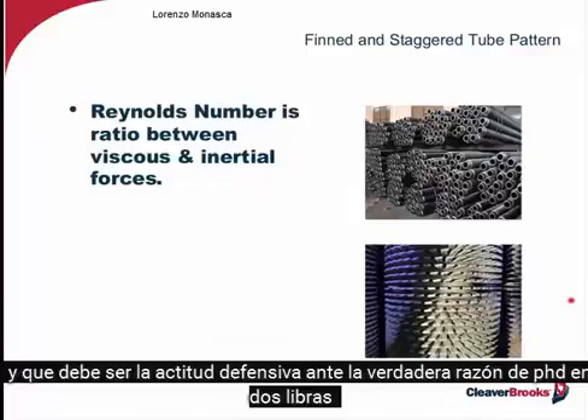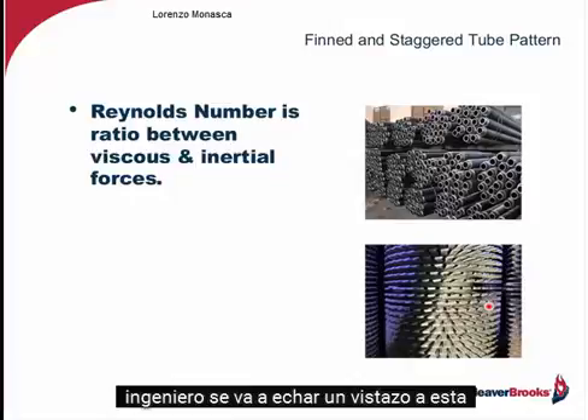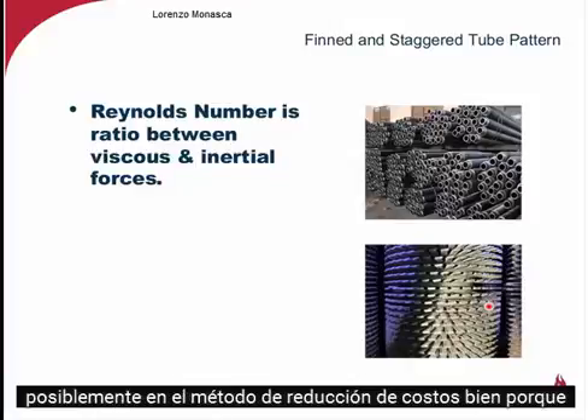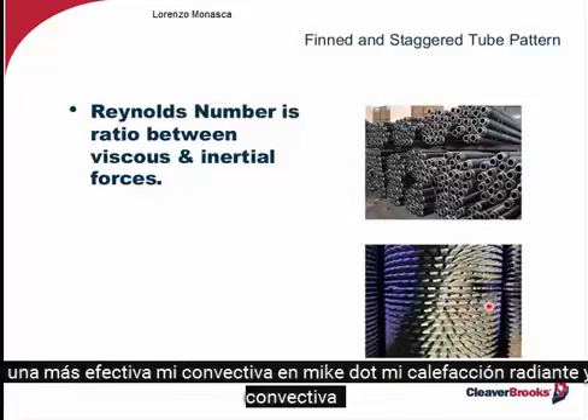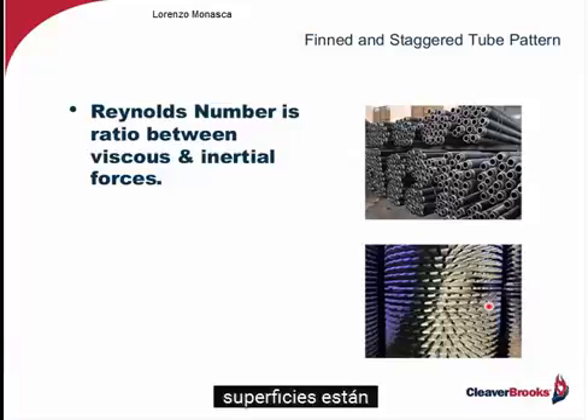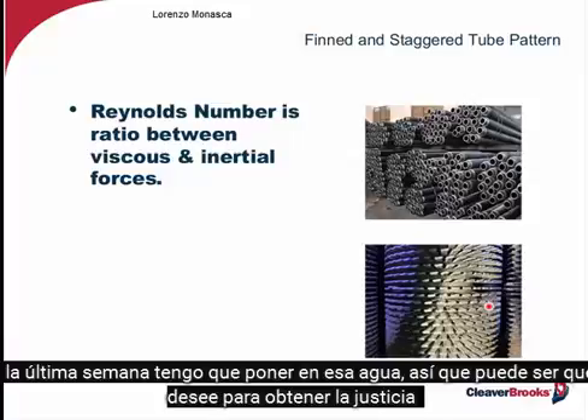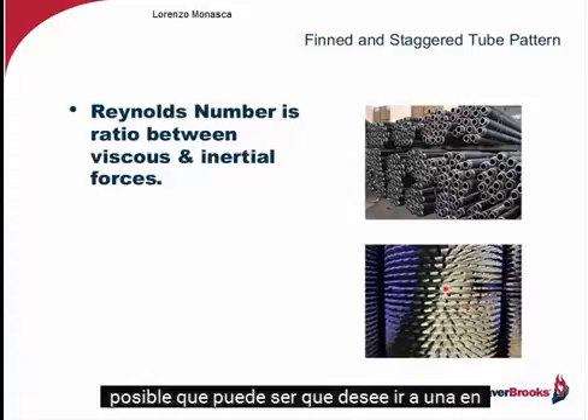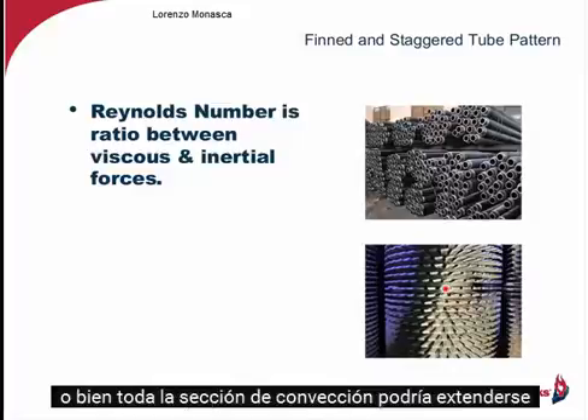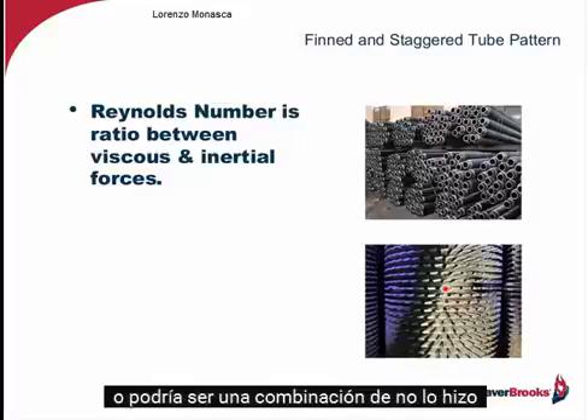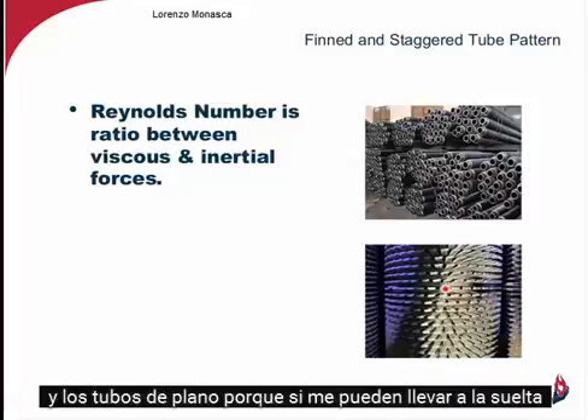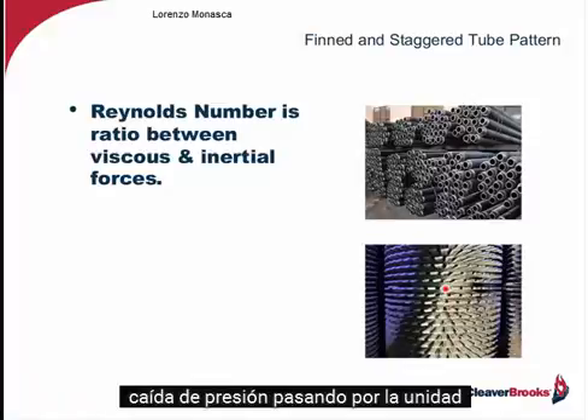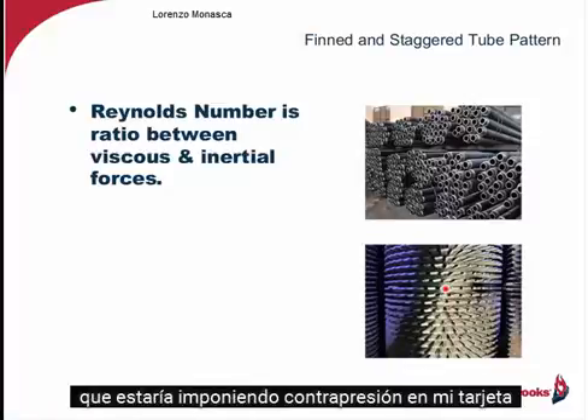I mentioned the fin tubes before. The main reason for fin tubes, an engineer is going to be taking a look at this. Possibly it's a cost reduction method, okay? Because the more effective my convective and my radiant and convective heating surfaces are, the less tubing I have to put in that boiler. So I might want, if it's possible, to go to a fin tube. Either the entire convection section could be finned, or it could be a combination of fin and plain tubes, because I can reduce the pressure drop going through the unit that would be imposing back pressure on my turbine.